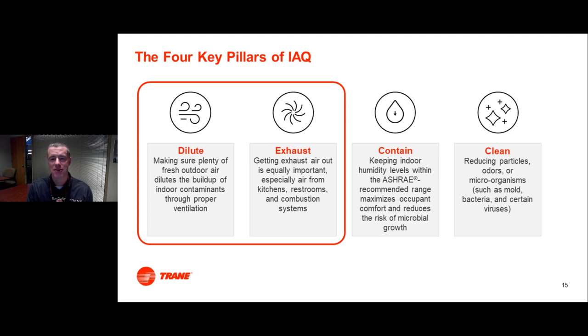Exhaust can be as simple as providing fans for exhausting air out of rooms, especially when you get to tighter rooms where they may have less air movement, such as restrooms or kitchens. I bring up restrooms because every time now in the pandemic, since the first three months of the pandemic, every time I walk into a restroom, my ears perk up listening for an exhaust fan. So you want to ensure that for small spaces that may have restricted airflow, you put in an exhaust fan and you turn that exhaust fan on to ensure that you can get contaminants removed out of that space.